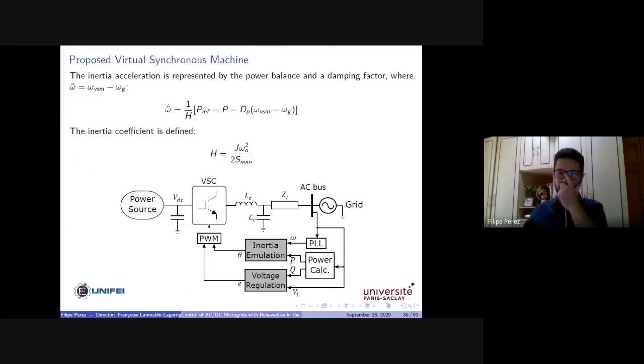And maybe I also have to, in the modeling of the grid, insert a transformer with a delta-Y connection to avoid the zero sequence harmonics, because when I have an unbalanced system, I will bring this kind of perturbation. So I should consider that the transformers of the system need to be changed. And mainly, I have to insert the control of the zero term from the Park transformation. That's what I think I should insert when considering unbalanced systems.